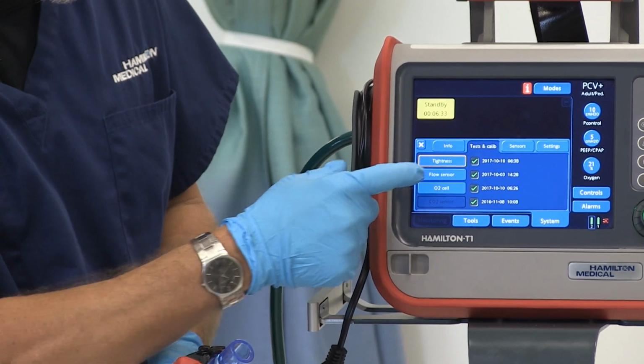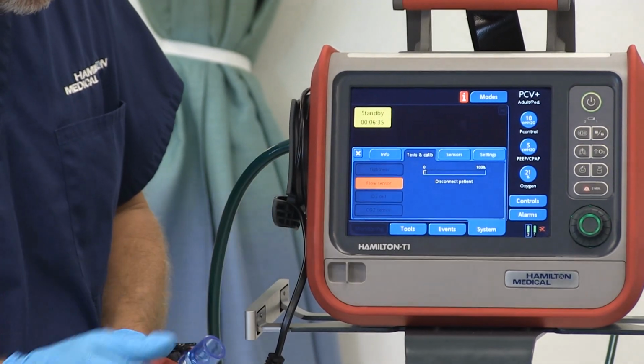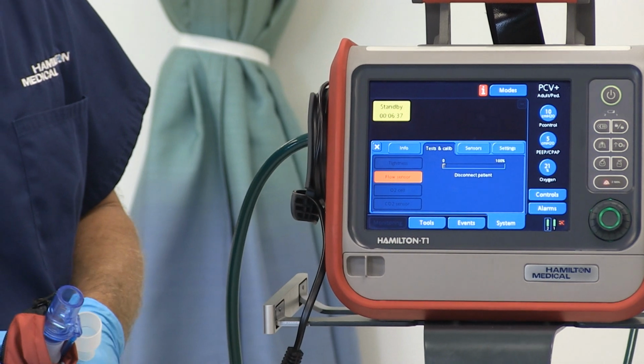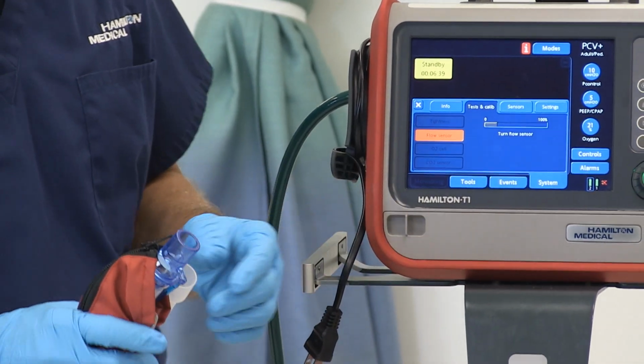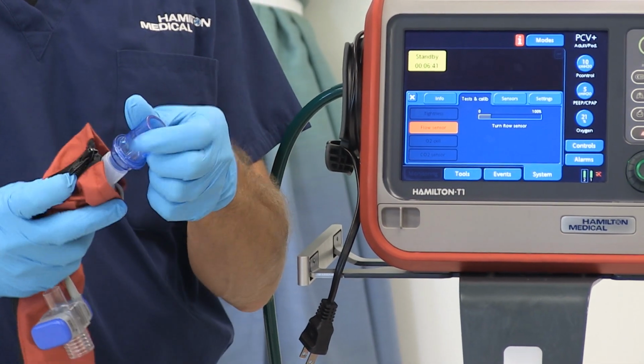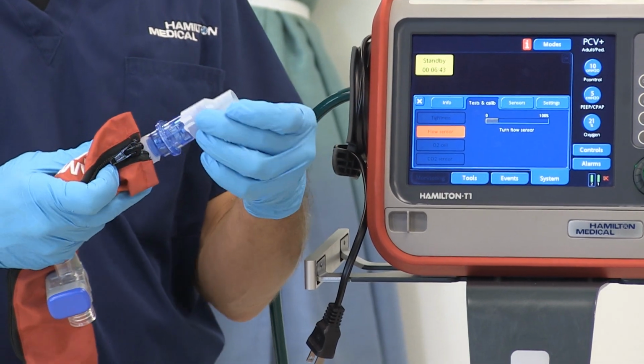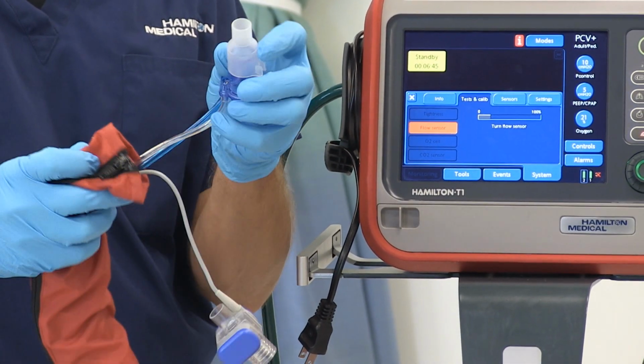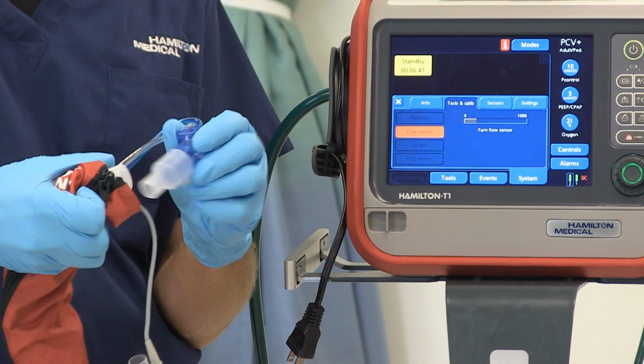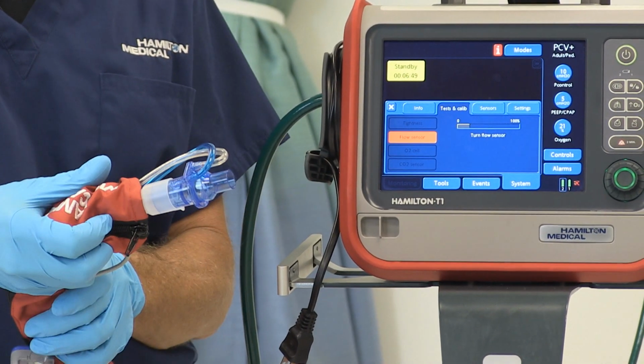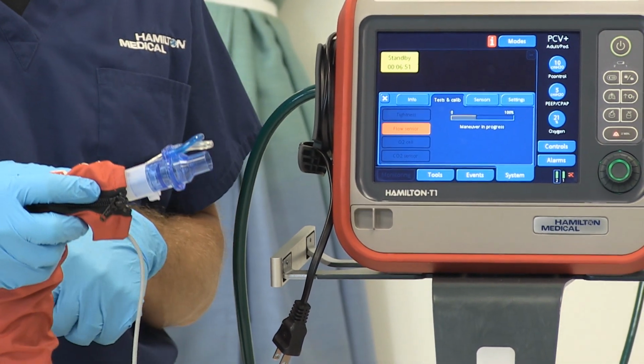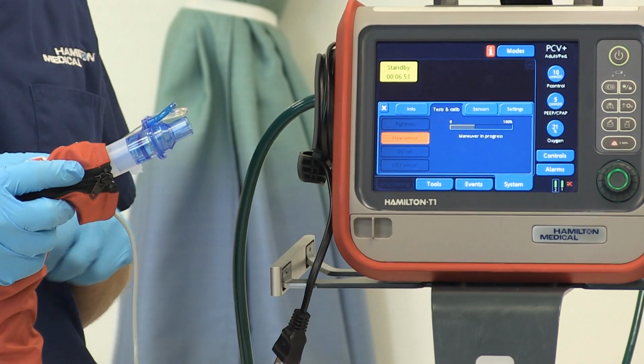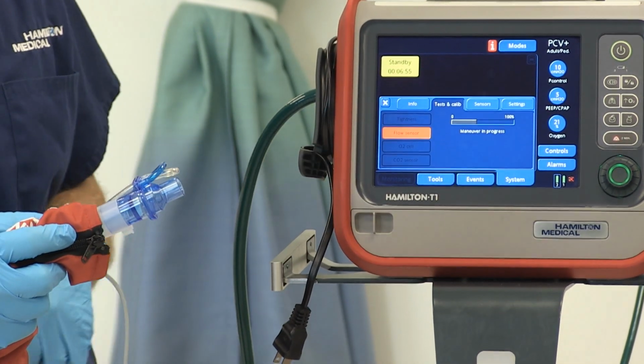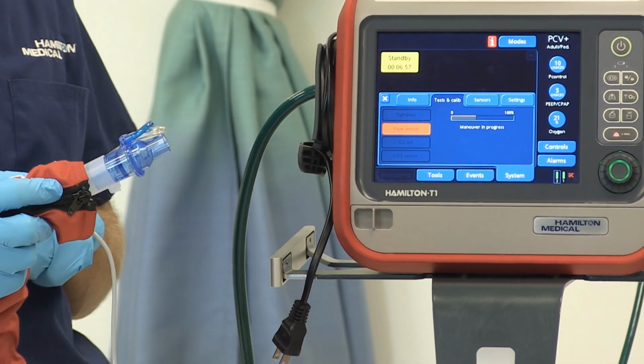It's called flow sensor. I depress that, and it tells me again what to do. It says disconnect patient. Now it says turn the flow sensor. So this is where I need my flow sensor adapter. Place it on the end of the flow sensor. Reverse the flow sensor in the circuit. And the ventilator will sense when I've reversed it, and we'll continue with the test. And so again, you need to watch the screen because it's going to tell you what to do next.